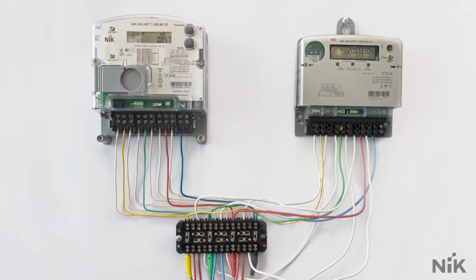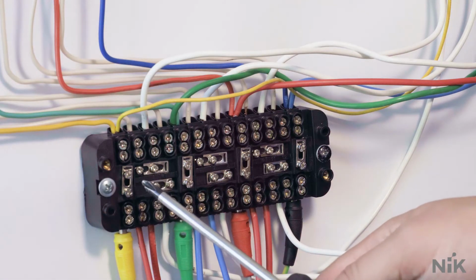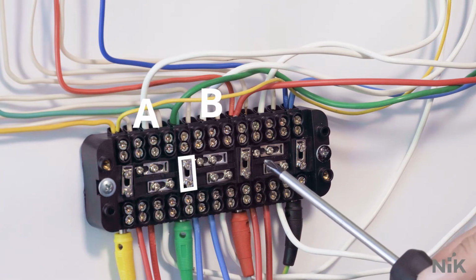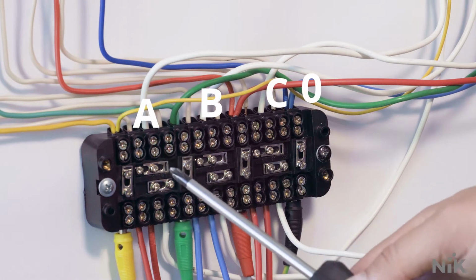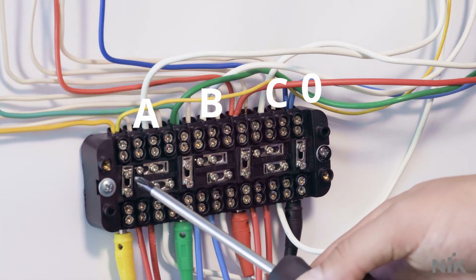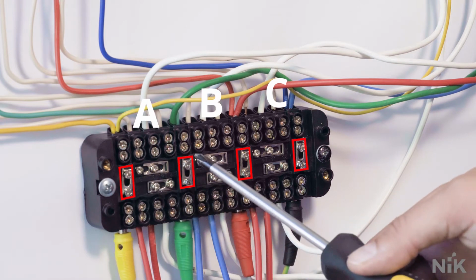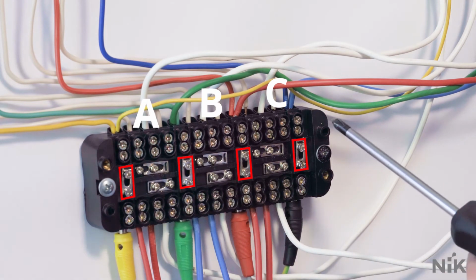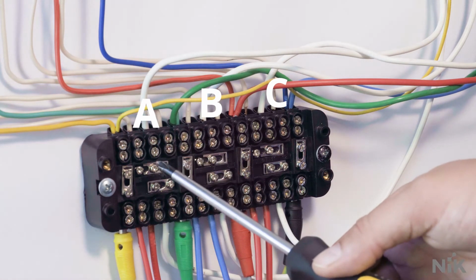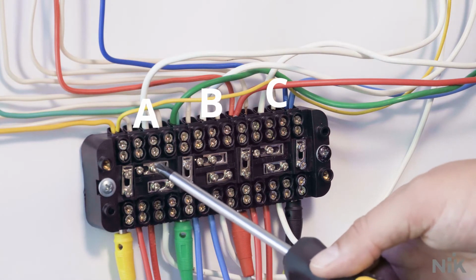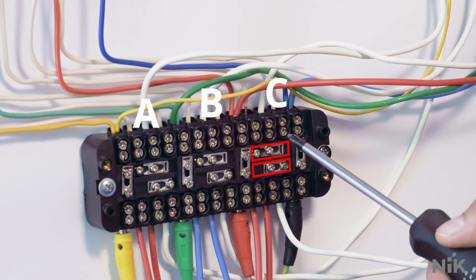First regime. The terminal block is in working position. There are voltage circuits, phase A, phase B, phase C, and neutral. The circuits can be disconnected using these vertical jumpers. Also, terminal block has horizontal jumpers for phase A, phase B, phase C.